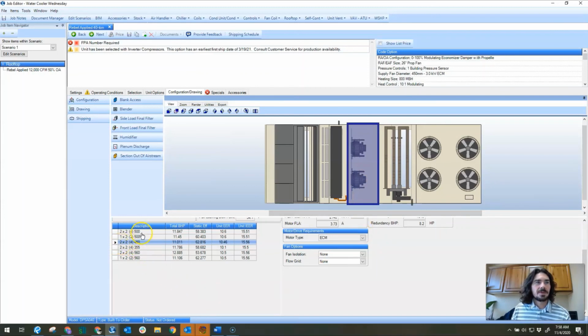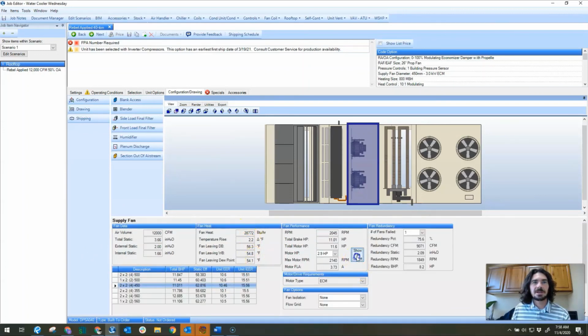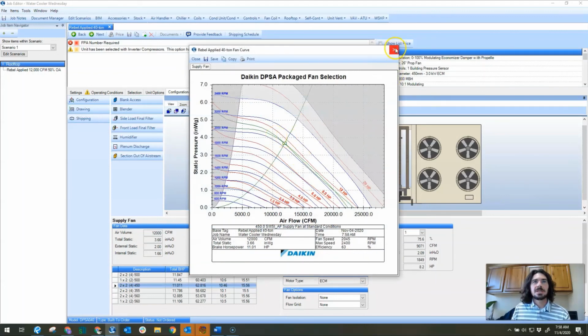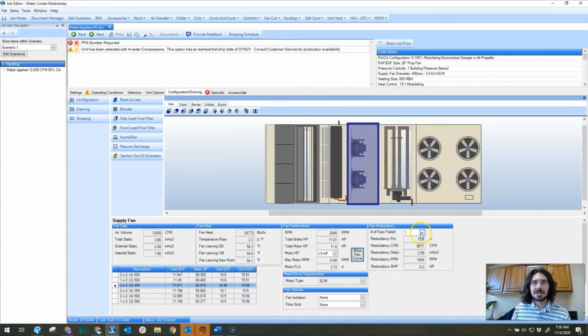So here we've got options for 1x2 or 2x2 fan arrays. I'm going to stick with the 2x2 array option, and we're going to check the fan curve here. So that looks pretty good. The other thing you can check here is when a fan has failed, it'll show you the redundancy percentage. You look at 1 or 2 fans failed. So it's kind of a neat feature also.